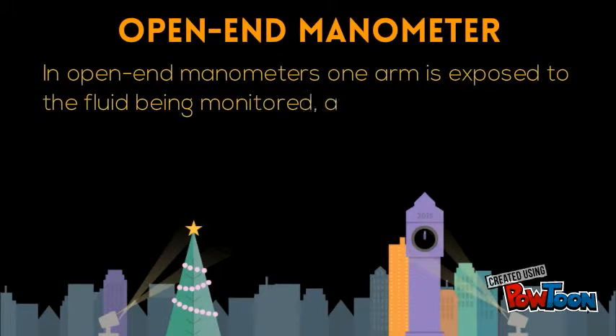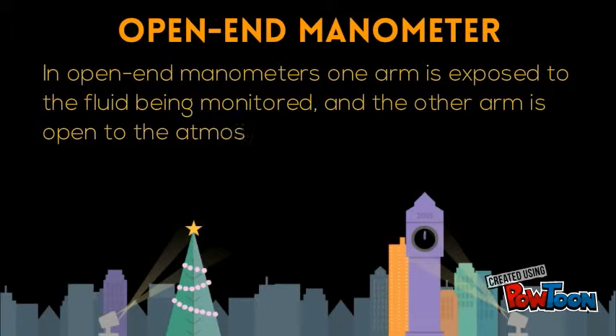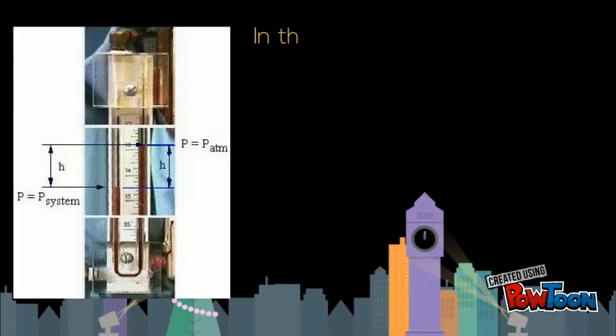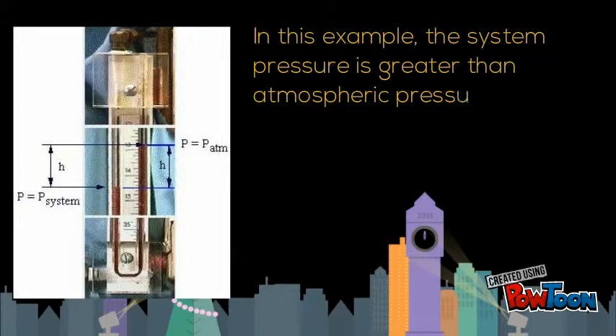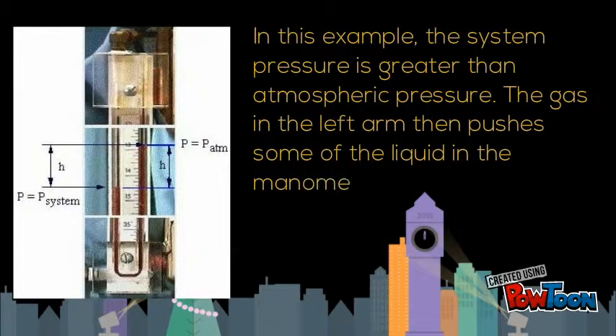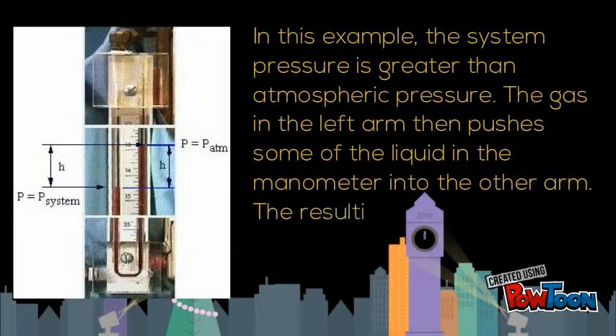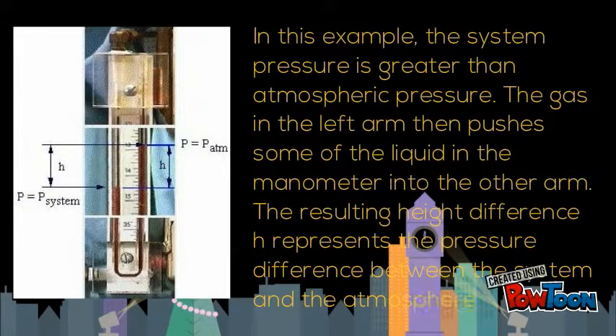In an open end manometer, one arm is exposed to the fluid being monitored and the other arm is open to the atmosphere. In this example, the system pressure is greater than atmospheric pressure. The gas in the left arm pushes some of the liquid into the other arm, and the resulting height difference, H, represents the pressure difference between the system and the atmosphere.